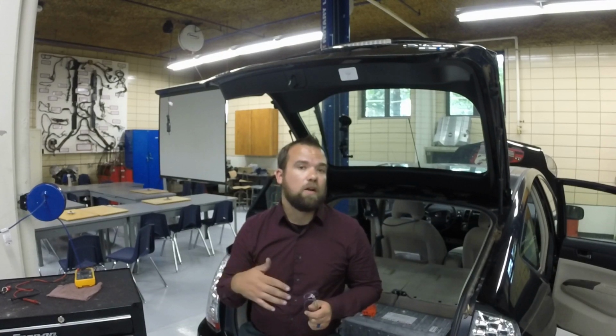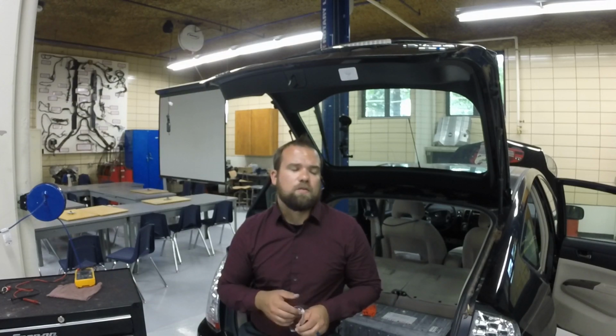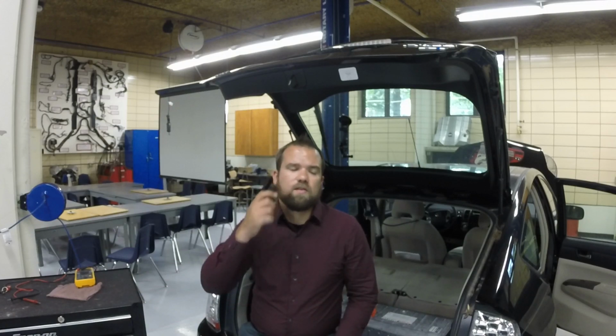Notice the meter at all times was away from my face. This is to prevent facial injuries should the meter have been tampered with or something like that. It's good practice even if you're using your own meter, especially if other people use it too. You never know if it's been dropped or if some of the circuitry's been damaged inside, so you really don't want to hook it to a circuit without knowing whether that meter's in good shape. Just good practices to stay in touch with.